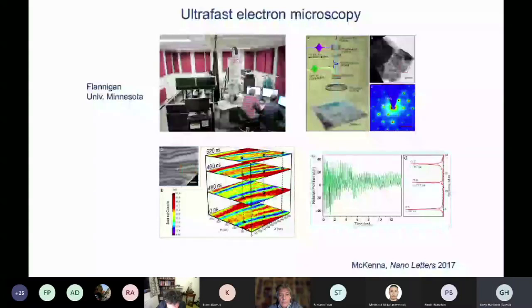The example at the bottom here is looking at some strain waves moving through a sample after exciting a material, and so you can sort of see these waves propagating through the material. So you can get very high spatial resolution with this technique. The time resolution is not that great because it comes from the electrons, and it's very hard to keep the electrons together in a little bunch as they pass through the sample. They repel each other, and that spreads out the electron pulse. The sensitivity is also really quite low. At least it hasn't very high sensitivity. Studies of small particles has not been demonstrated so far.